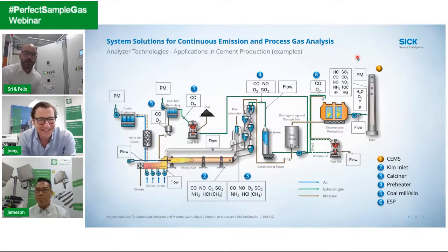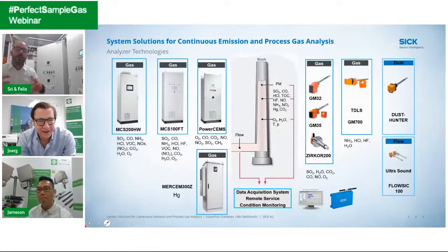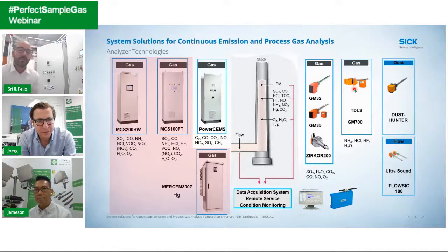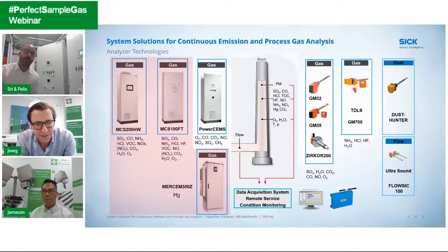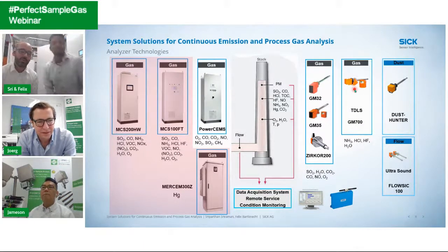So coming to the next slide, I just want to give you a short overview about our product portfolio for emission monitoring and process gas analysis. We can start with the hot wet measurement solutions, for example the MCS 200 HW, the MCS 100 FT, and the MERCEM300Z, where the sample gas from the probe to the final analyzer is always kept above the dew point at 200 degrees Celsius, so we can make sure there is no condensation happening inside the probe, the sample line, and the analyzer.